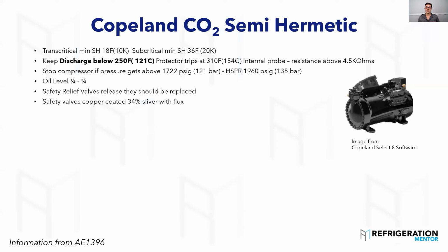Safety valves copper coated, 34% silver solder with flux when you're brazing these in. Highly recommend practicing with that. There's a lot of components in with CO2 that are stainless steel, so you're doing dissimilar metal brazing. So just make sure that you understand how to do that.